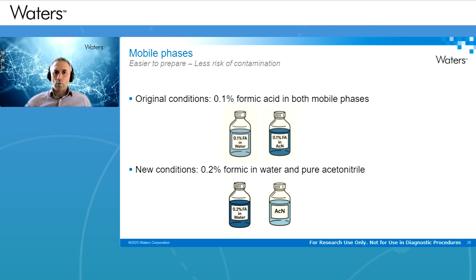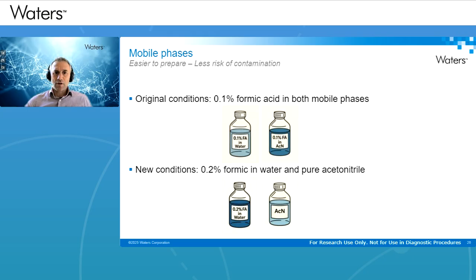While we were optimizing gradient and column conditions, we equally thought whether we could optimize the mobile phases. We changed the original conditions, which was 0.1% formic acid in both the mobile phase A and B. We changed them into 0.2% formic acid in the aqueous mobile phase, while at the same time removing the formic acid from the organic mobile phase. This actually simplifies the preparation of the mobile phases and minimizes the risk of introducing a contamination.